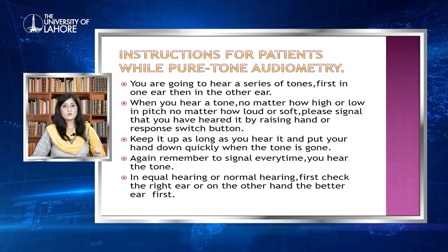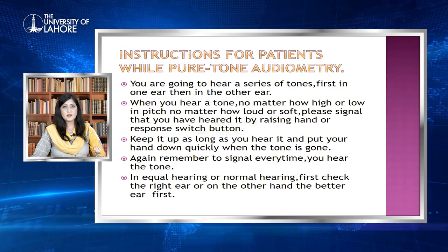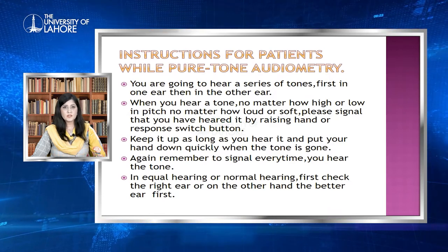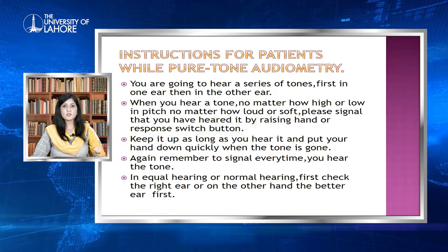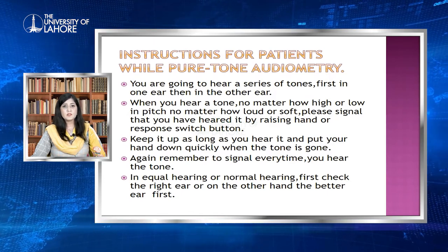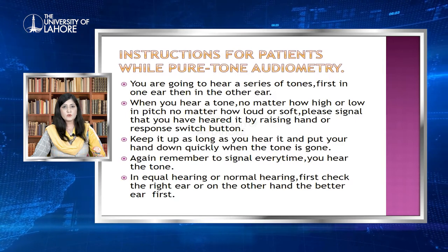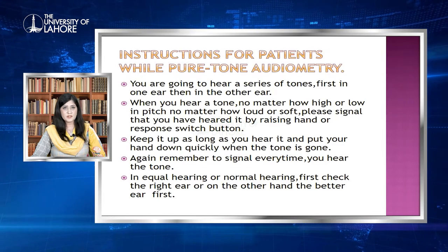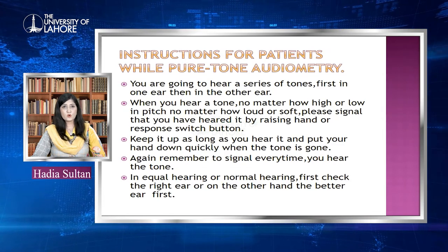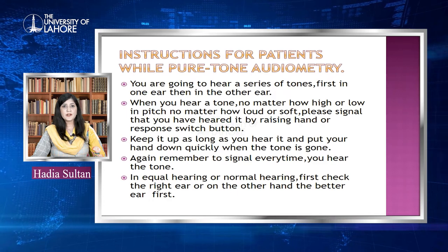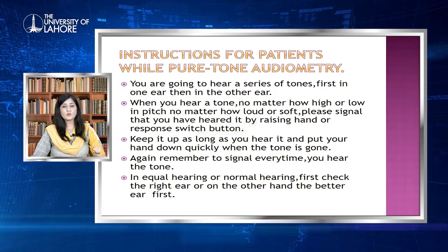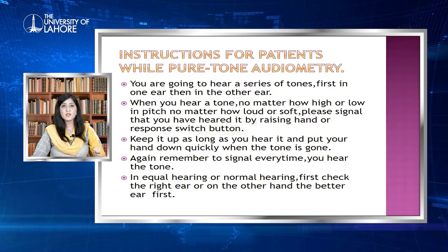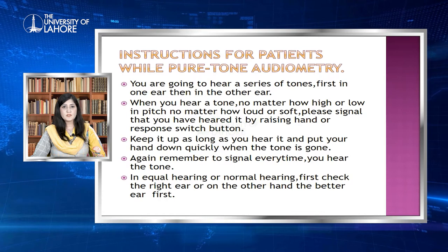The instructions to give the patient are: you are going to hear a series of tones, first in one ear and then the other. When you hear a tone, raise your hand or press the switch button. Keep it up as long as you hear it and put your hand down — or release the button — when you are no longer hearing the sound. Remember to signal every time you are listening to the tone.